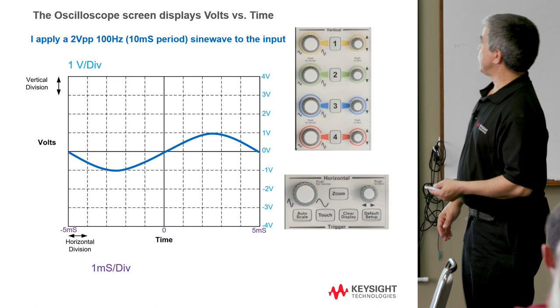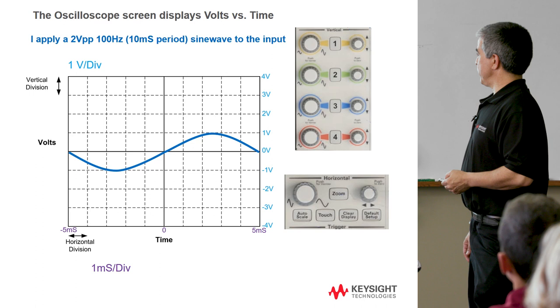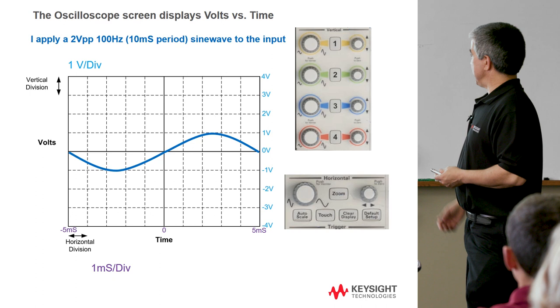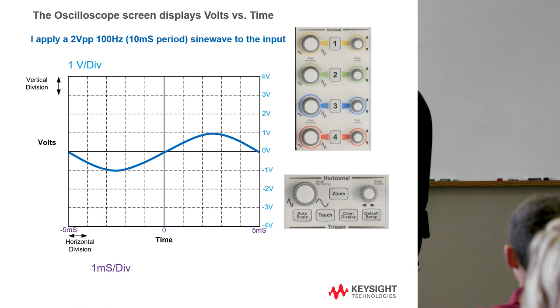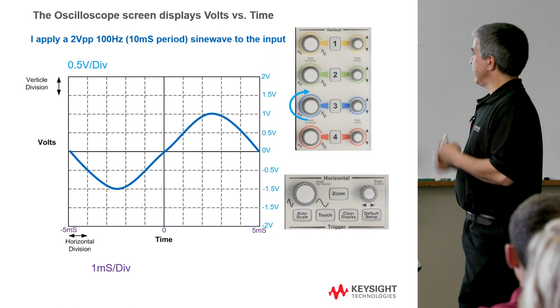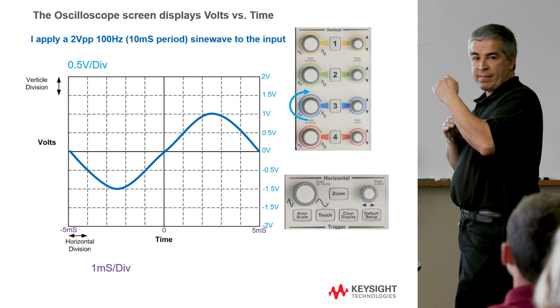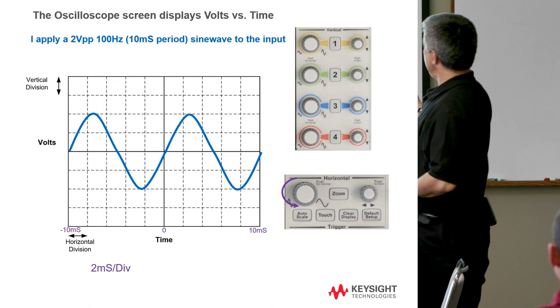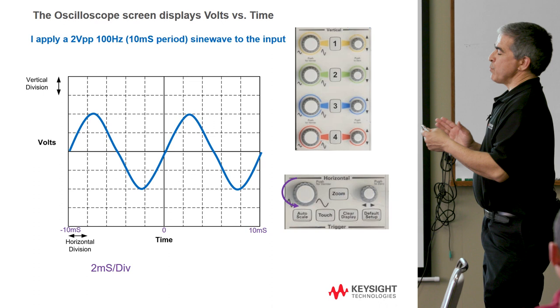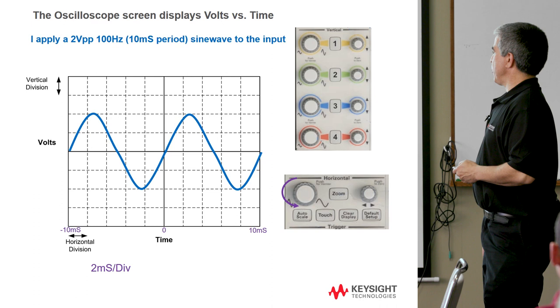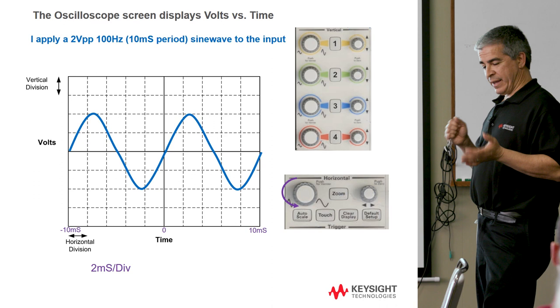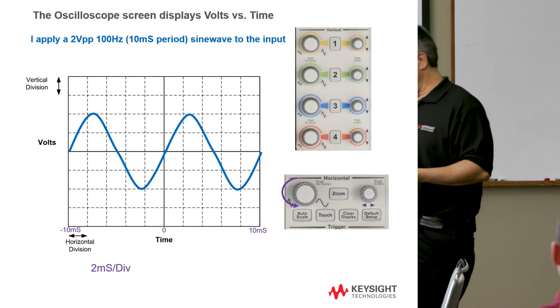Let's assume we applied a two volt peak-to-peak 100 hertz sine wave, and we've got it set to one volt per division and one millisecond per division. That's got a 10 millisecond period. So the waveform on screen will look like something that's two volts peak-to-peak. If we want to magnify that signal or cover more of the screen, we'd change the volts per division to half a volt per division, which effectively makes the signal look bigger — it's not really a bigger signal at the input, it's just scaling the signal so the downstream A-to-D converter can use more of its range. Moving the horizontal from one millisecond to two milliseconds per division gives us two periods on screen.